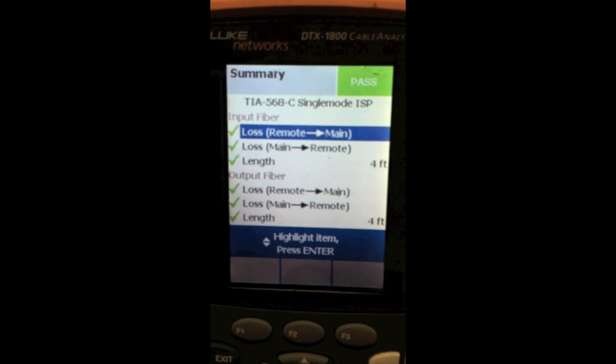Okay we actually have a negative loss found in the test result. And if you ever get this message it's not a bad thing. It just means that as the test went on the connection got better. So we're going to take a look at the results here. On our input fiber we see that our loss has checked off good. And the direction being that the light is traveling from our remote here back to the main is good.